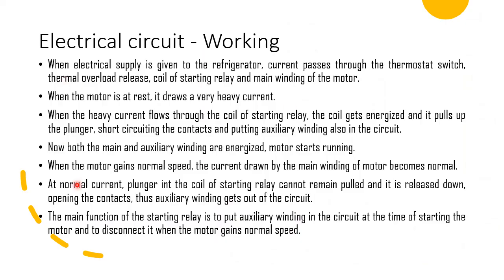So here the same thing is written here. When the electrical supply is given to refrigerator, first current passes thermostat switch. This thermostat switch is used to maintain the temperature. Next again to the thermal overload release, a protective device of a motor, and then the coil of starting relay, and then main winding of motor. Now the motor is at rest. It draws very heavy current.